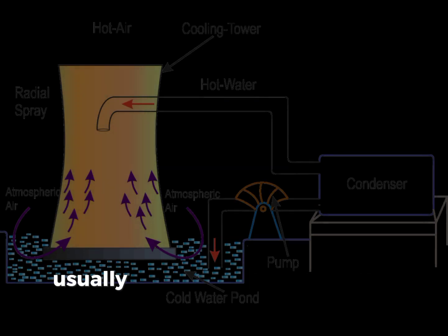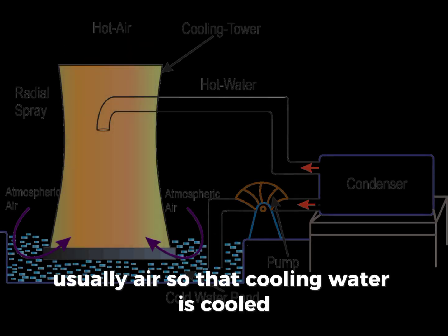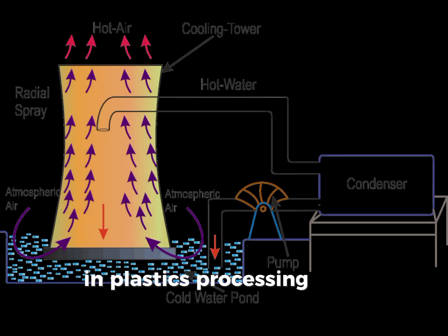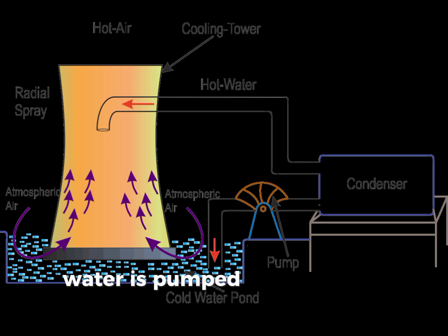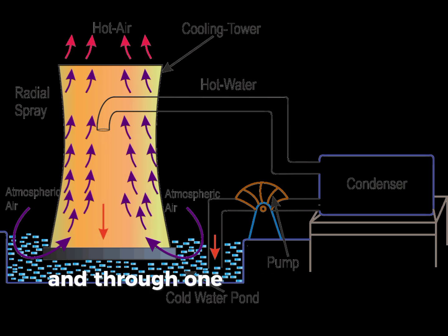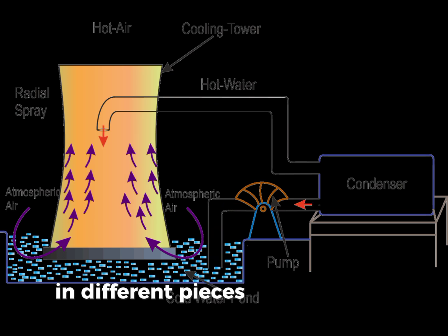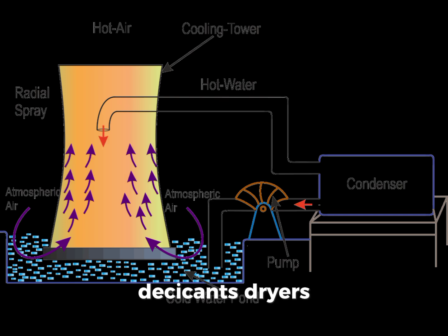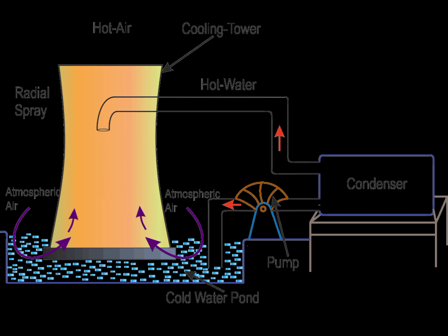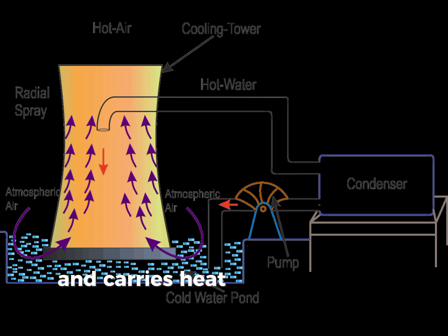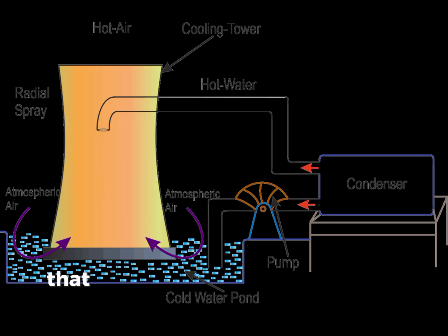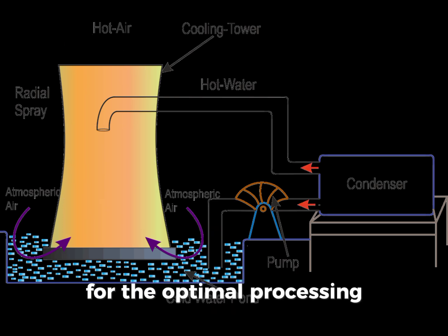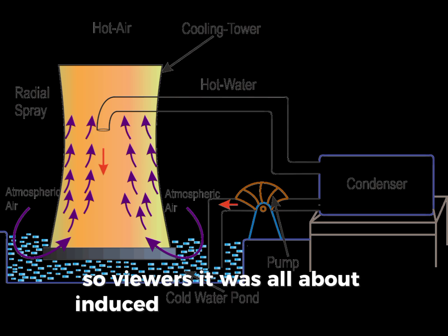A cooling tower extracts heat out of the cooling water and pushes it into another medium, usually air, so that the cooling water is cooled and ready to be recirculated. In plastics processing, cooled process water is pumped out from the cooling tower base and through one or more cooling circuits in different pieces of equipment such as processing tools, molds, desiccant dryers, and water-cooled chillers. The processed water absorbs and carries heat away from the equipment so that operating temperatures stay within the range required for optimal processing.